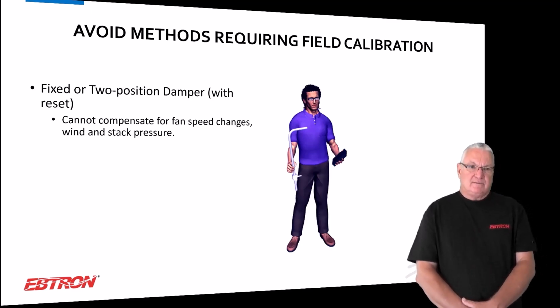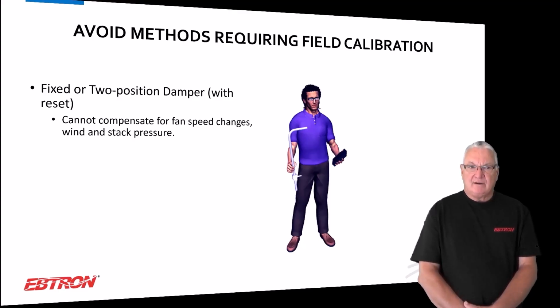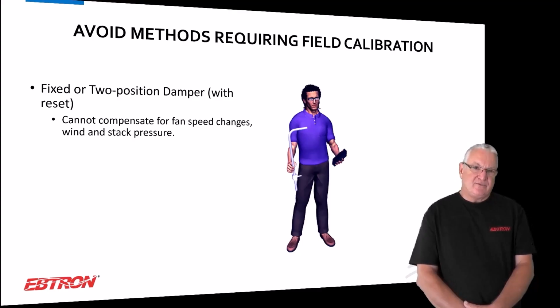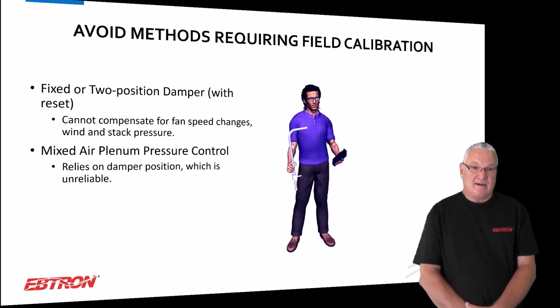Well, we talked about damper position already, so that should be out. You can't compensate for fan speed changes, wind speed, stack pressure. It doesn't matter if it's one or two position, and you have all these damper problems. So that should be out.